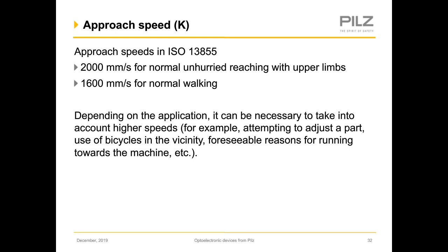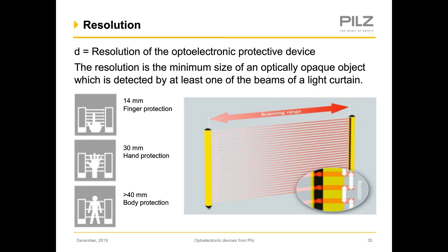And within the calculation, also our resolution is a factor. So we touched on this, resolution D, 14 millimeters for finger, 30 millimeters for hand, and larger than 40 millimeters for body protection.